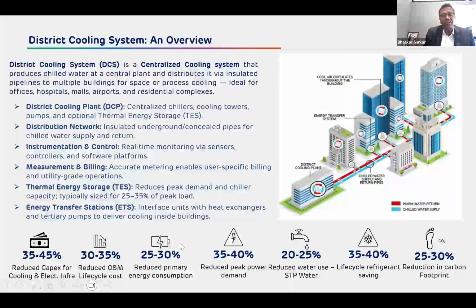The primary energy consumption becomes lower, because the conventional chillers or conventional air conditioning mechanisms have an efficiency of 1.1 to 1.5 kW per TR. That means to generate 1 TR, they consume 1.1 to 1.5 kilowatt hour of energy, whereas a DCS system consumes about 0.75 to 0.8, so about 40 to 50% less. So the primary energy consumption is quite low. The peak demand is also lowered, because as I said, it can be substituted with thermal energy storage, and also the diversity of the peak loads across various consumers can be clubbed together, so that the overall peak to be fed becomes lower.